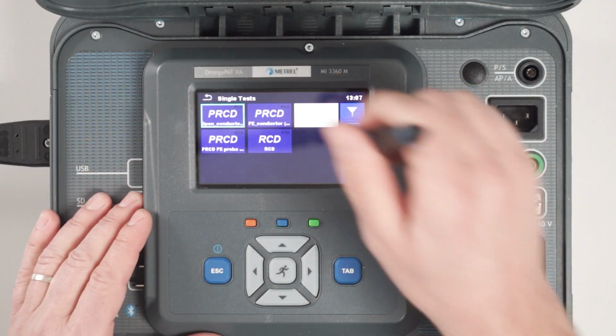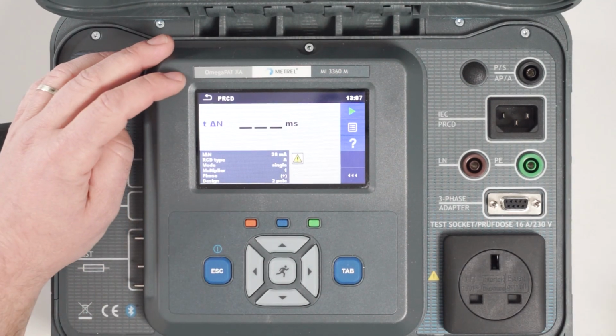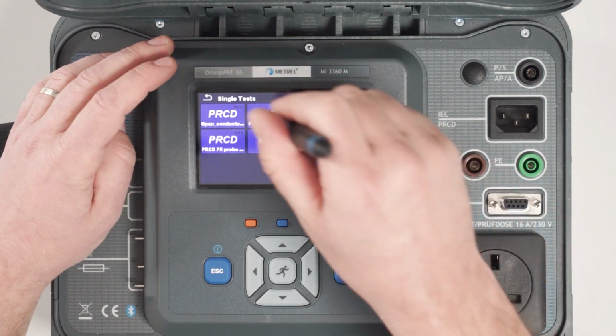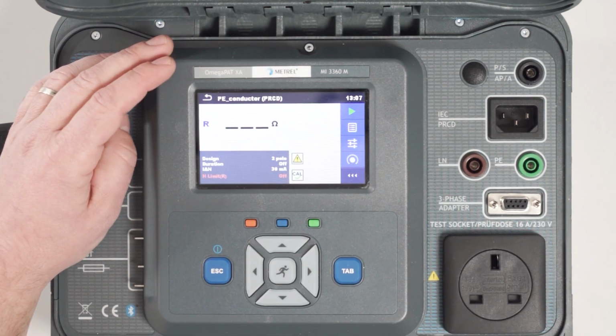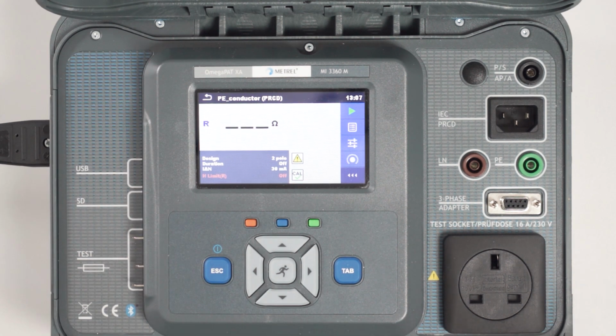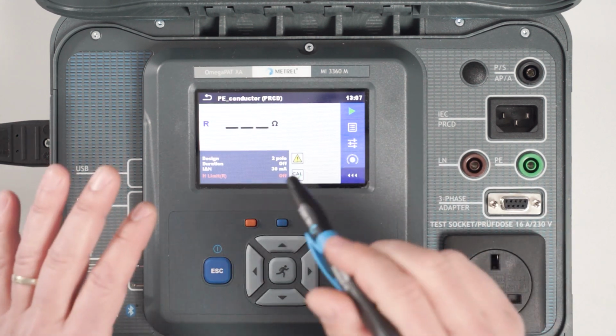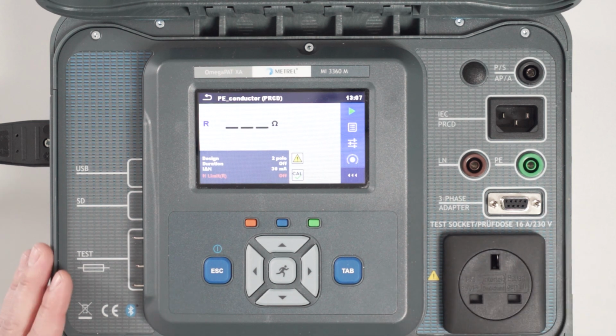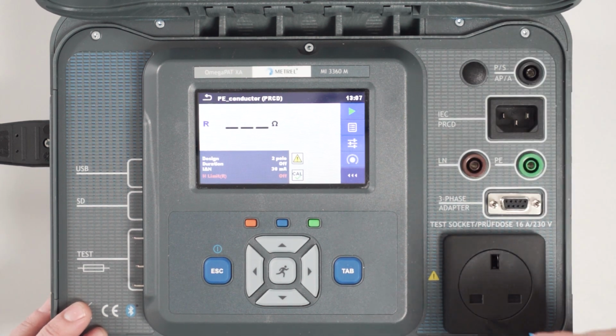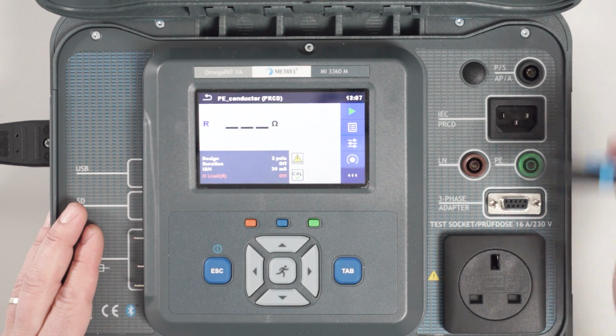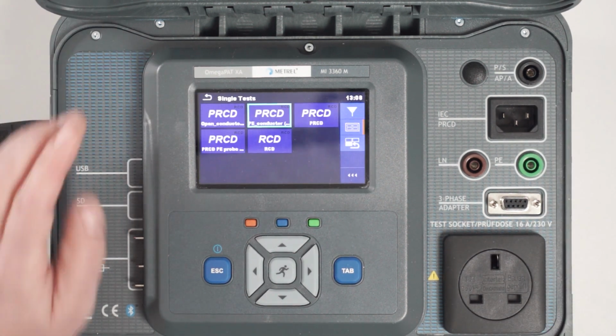Inside this menu for portable RCDs we have the option to measure trip out time. Then we have the possibility to measure PE conductor of the RCD. So in case we have an RCD which needs to be armed during the measurement of PE, we will apply during this measurement the full voltage, and we will measure the PE or the earth resistance of our RCD.